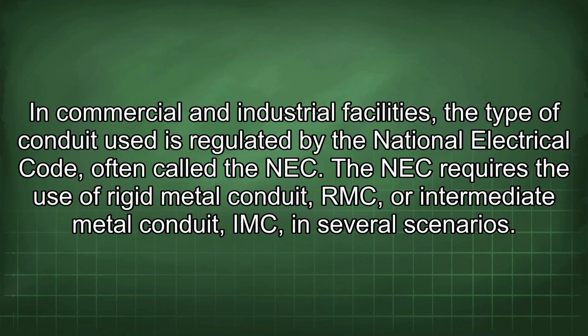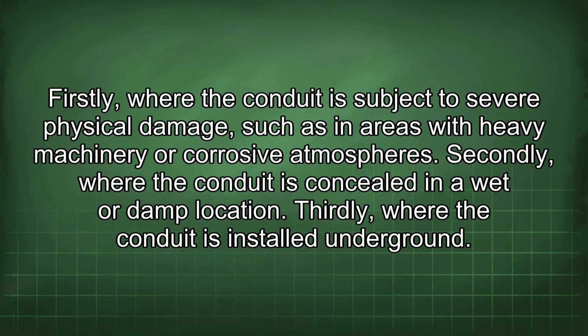In commercial and industrial facilities, the type of conduit used is regulated by the National Electrical Code, often called the NEC. The NEC requires the use of rigid metal conduit, RMC, or intermediate metal conduit, IMC, in several scenarios. Firstly, where the conduit is subject to severe physical damage, such as in areas with heavy machinery or corrosive atmospheres.